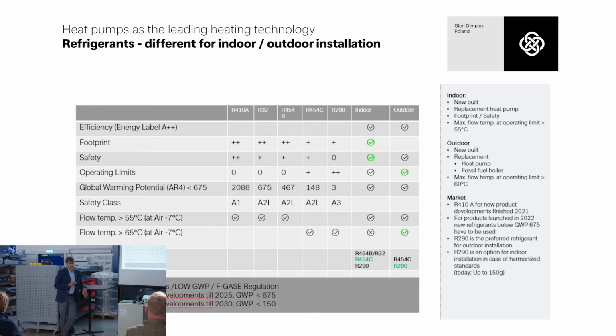For indoor machines, propane is not okay. At the moment, our regulations don't allow us to build heat pumps with propane inside. So the alternative refrigerant is R454C. It is also okay because it is safe. It has an acceptable operating range, and it is very nice because of the footprint of the device. So the space and the size of the device are as small as possible, just for saving space in the plants, in the room where the machine is installed.